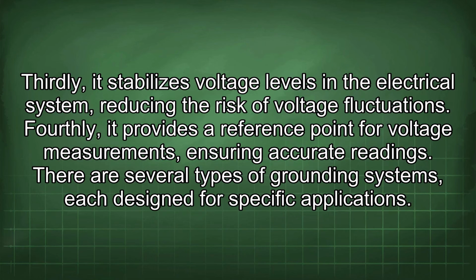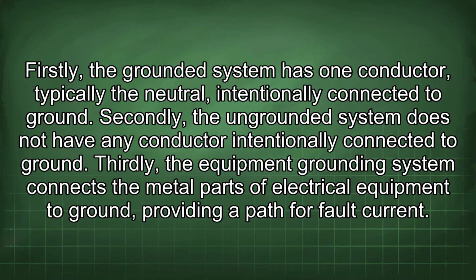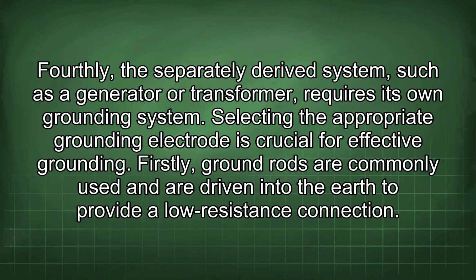There are several types of grounding systems, each designed for specific applications. Firstly, the grounded system has one conductor, typically the neutral, intentionally connected to ground. Secondly, the ungrounded system does not have any conductor intentionally connected to ground. Thirdly, the equipment grounding system connects the metal parts of electrical equipment to ground, providing a path for fault current. Fourthly, the separately derived system, such as a generator or transformer, requires its own grounding system.